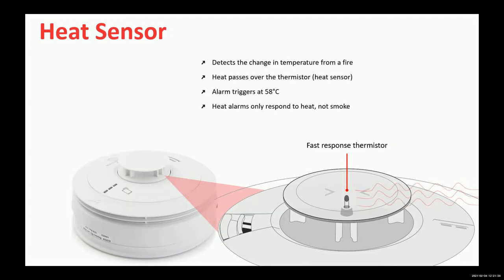And if we look at that, it detects the change in temperature from a fire. Heat passes over the thermistor, and again, under the standards, we have to set that at between 54 and 62 degrees. So we trigger that thermistor at 58 degrees C, and it only responds to heat and not smoke. We do get a lot of calls into the office in relation to the heat alarm in the kitchen going into alarm.